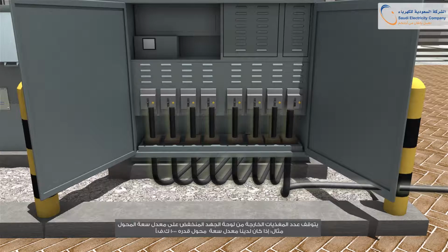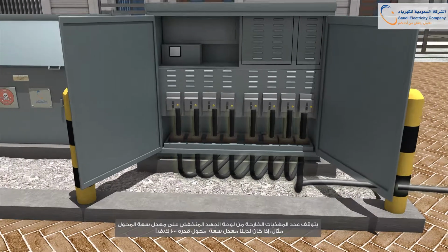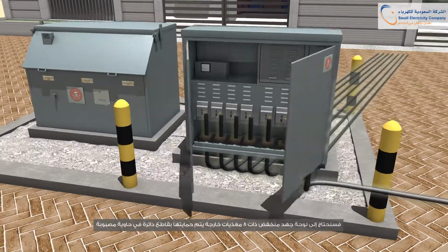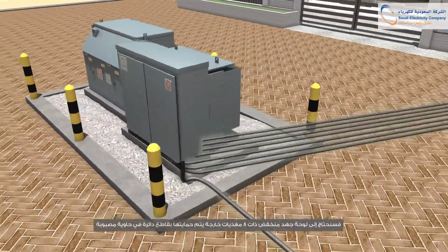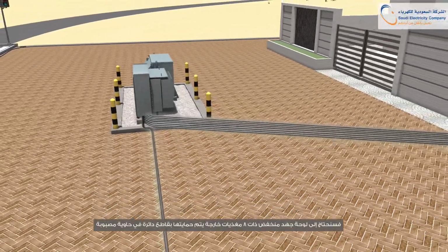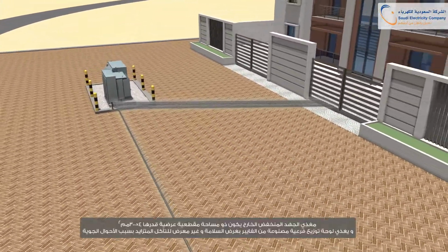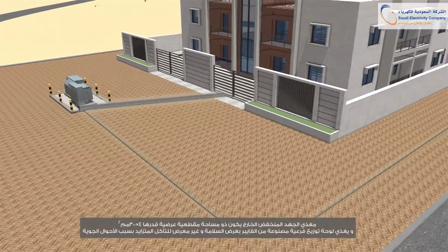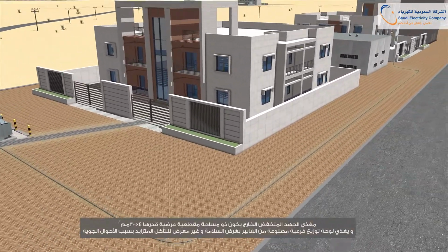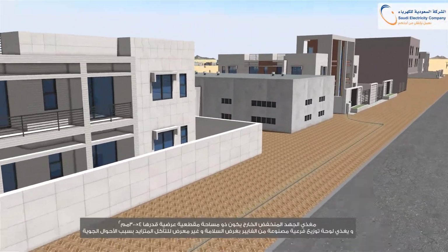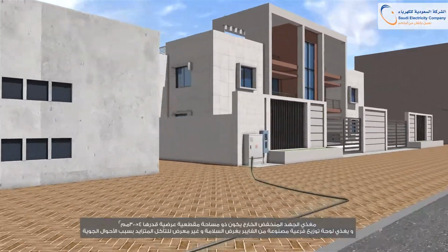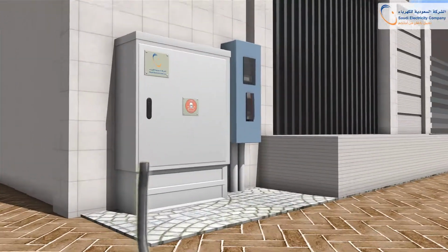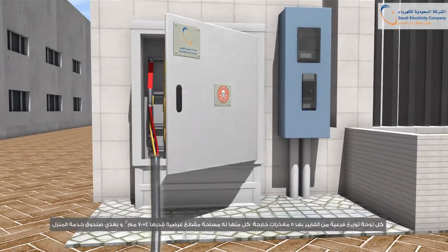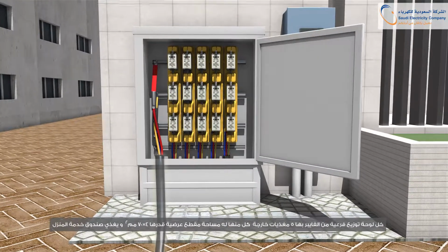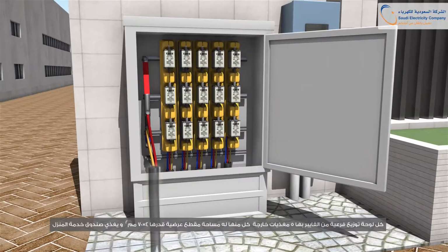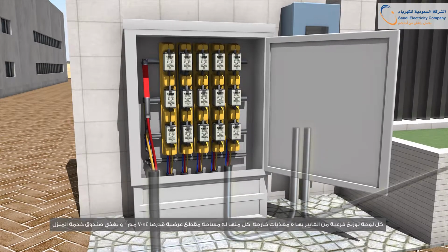For example, if we have a transformer rating of 1000 kVA, we will need an LV panel that has 8 outgoing feeders protected by a molded case circuit breaker. The outgoing feeder of LV has a cross-section area 4 by 300 square millimeter and feeds a mini pillar made of fiber for safety and is not subject to increased corrosion due to weather conditions. Each fiber mini pillar has 5 outgoing feeders. Each of them has a cross-section area 4 by 70 square millimeter and feeds the house service box.